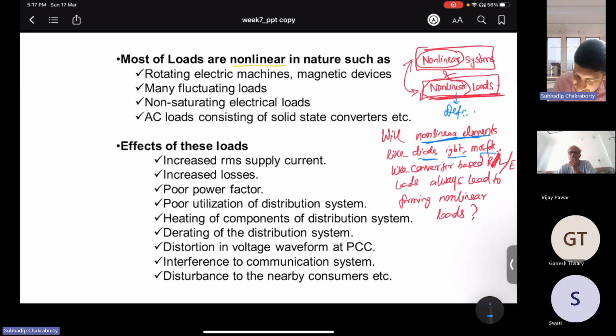So definition wise, we can write nonlinear loads mean V not proportional to I, or VL not proportional to IL. The voltage across the load and the current going into the load are not proportional. They are classified as nonlinear loads. But to become a nonlinear load, do the loads always have to be used with some nonlinear elements, or can linear elements also lead to the formation of nonlinear loads? Or can these nonlinear elements, like diode based, IGBT based or MOSFET based devices, also form linear loads? This concept is very important.